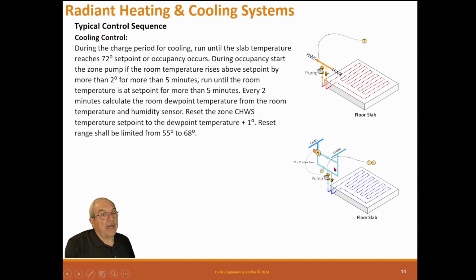So basically what's happening here is we have a temperature loop up here that takes cold water, then warms it up with return water, so we're always above dew point. We don't want to have any water on the floor, so we do that. Now this can also work where these zones are in walls or in the ceiling. They don't have to be in the floor. Same with this one, but traditionally it's normally been on the floor because that's where the mass is. These are mass cooling and mass heating systems. They're very, very effective. They're very comfortable, and they're very energy efficient because of the mass.